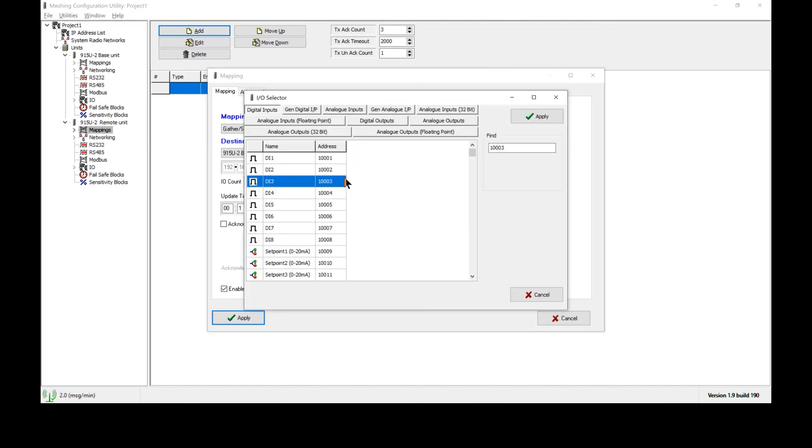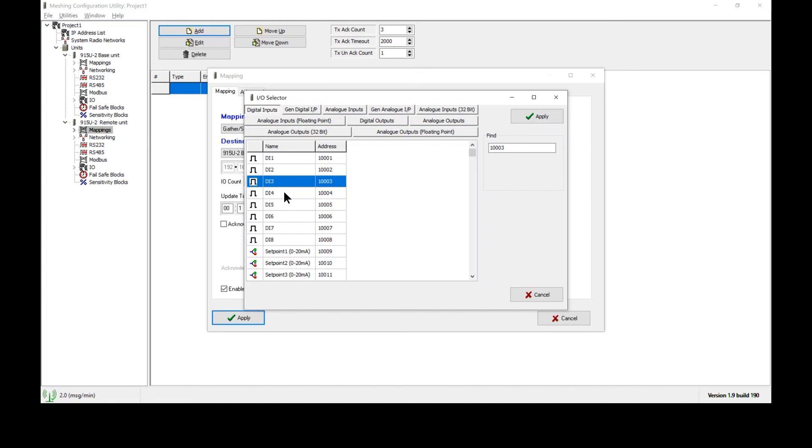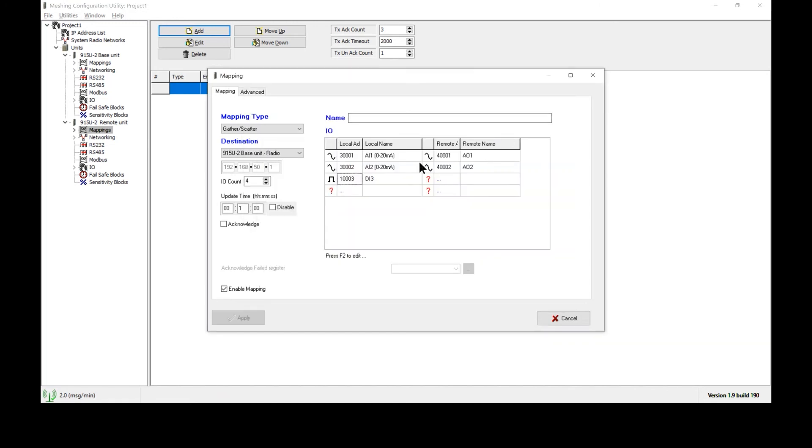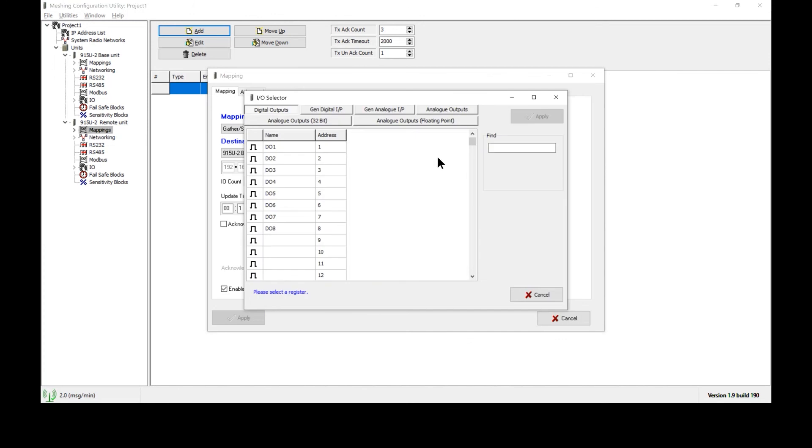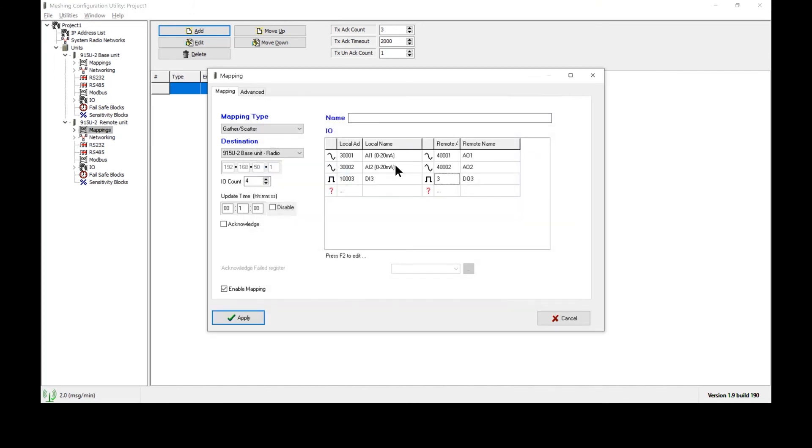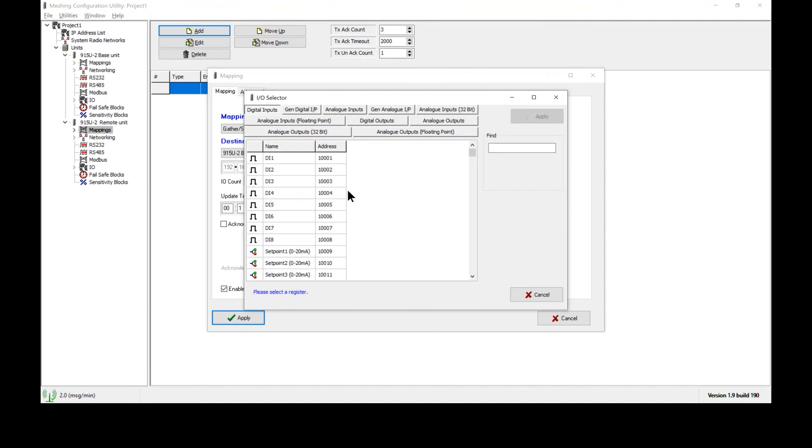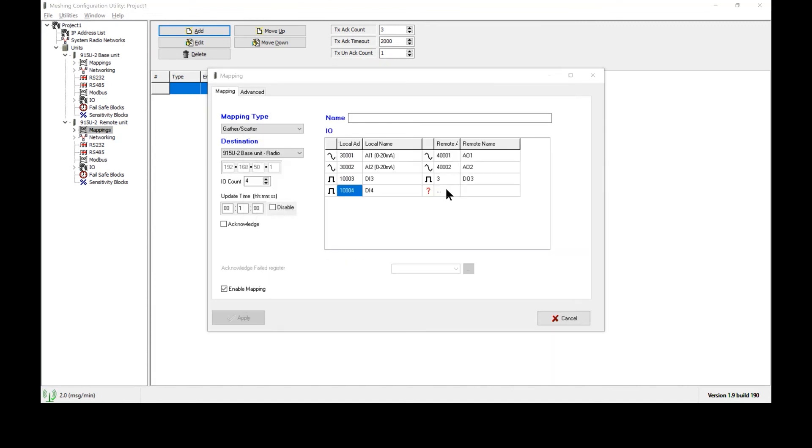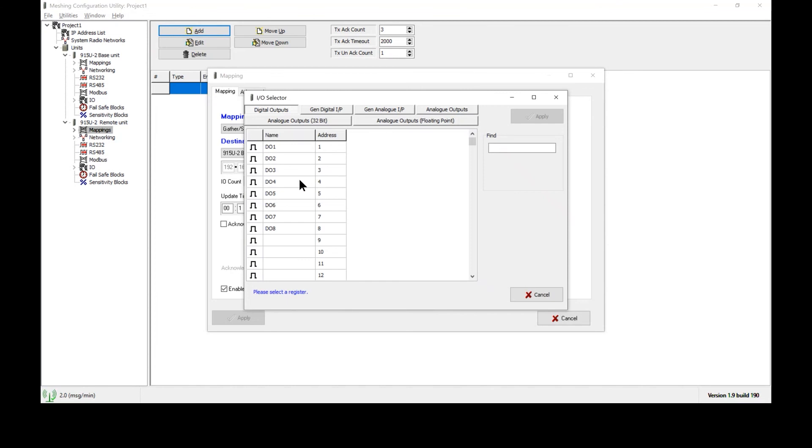Next, we repeat the process for digital inputs one and two. Now, remember that we have already used DIO one and two for the previous, for sending the data from the base radio to the remote unit. To send the next two digital values from the remote unit back to the base unit, we will use channels D3 and D4. Now, the 915U2 has eight DIO on it. They can function as inputs or outputs depending on how we program them here. So, we'll start with DI3 and we'll send it to DO3 on the opposite radio. We'll repeat the process with DI4, sending it to DO4 on the opposite radio.